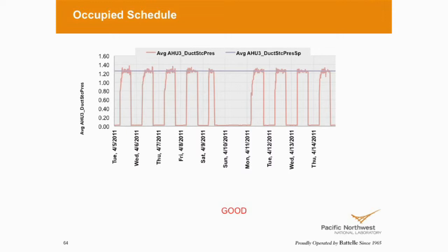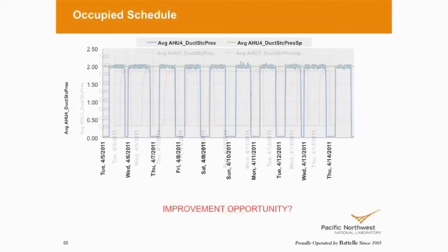No. In fact, we see a lot of people put abbreviated schedules on the weekends because they know, as someone said earlier, Mondays after 3-day weekends are notorious for recovery. So we see a lot of people put in maybe a 6-hour schedule just to maintain that building, so the mass is not as much of an issue when trying to recover.